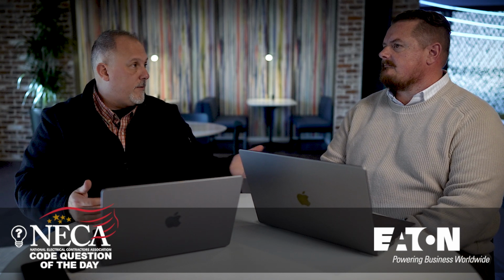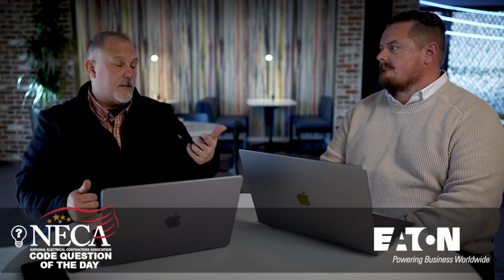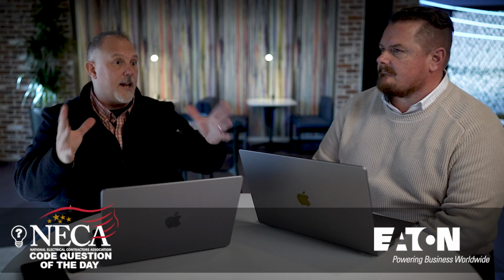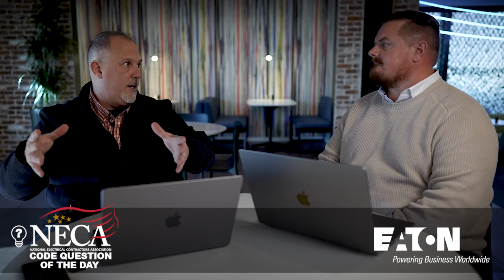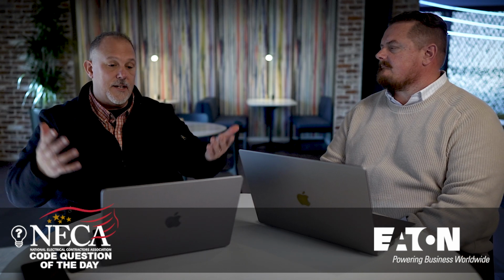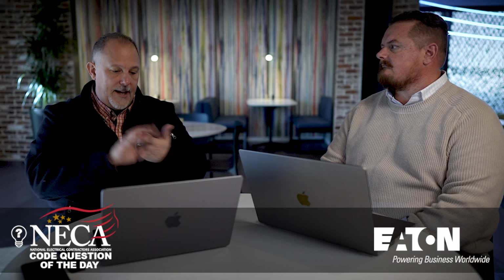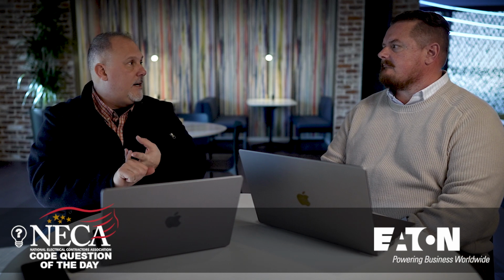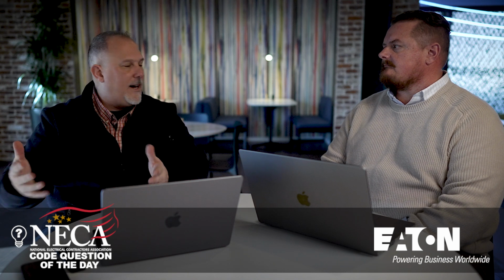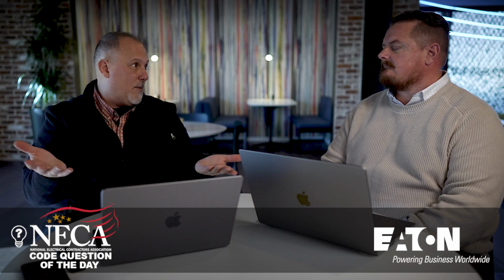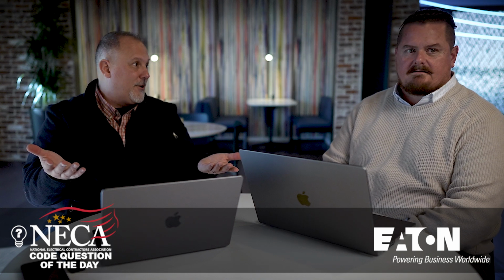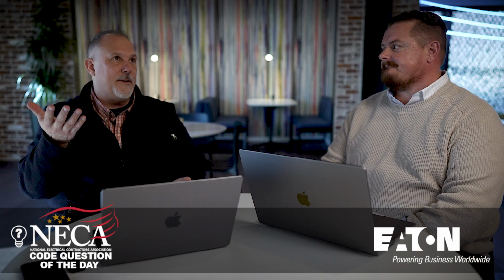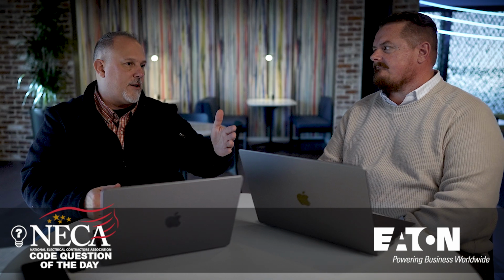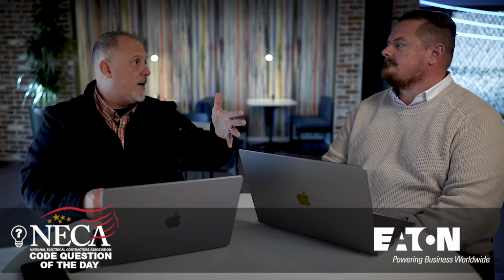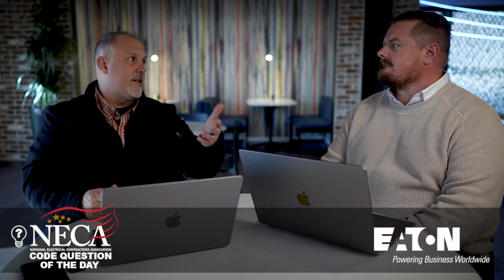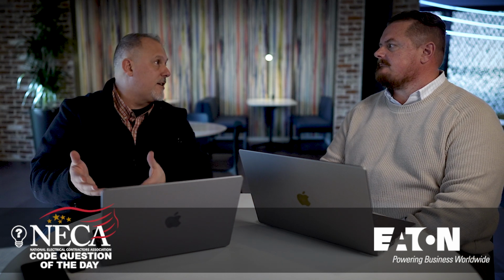Now, a 1-to-1 transformer, which is what I've seen on elevator control panels. In fact, one of the manufacturers actually has a catalog number to buy a 1-to-1 transformer. And then I got the call from the design engineer who says, well, now that I have a transformer on the roof, A, I have to find space for it. B, I'm in Article 450. I need to have primary and secondary protection if it's a delta Y ground transformer, which it probably is. Yeah, if you go with primary only protection, then you've got to look at what piece of equipment you're supplying. If it's a panel board, then you're going to need secondary protection on the secondary of the transformer.